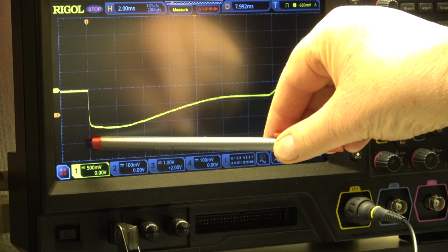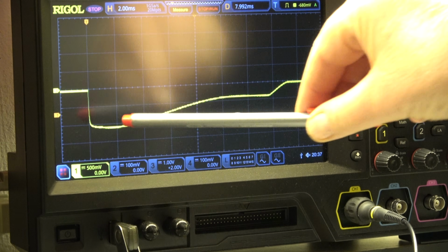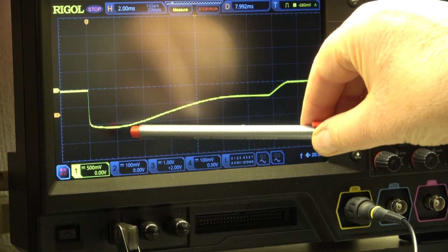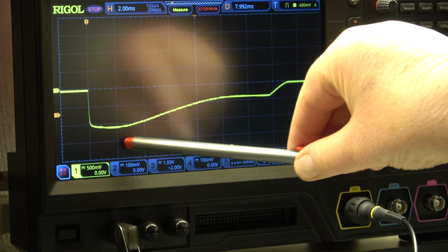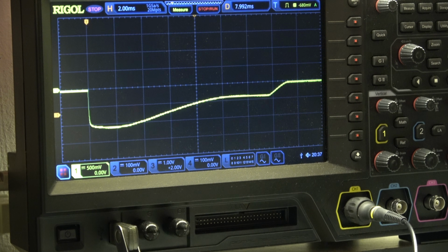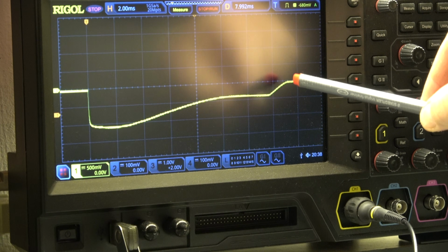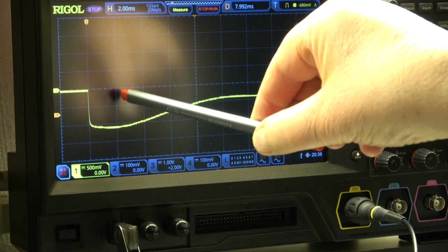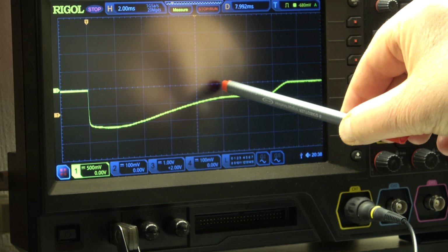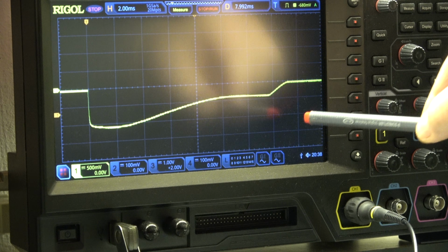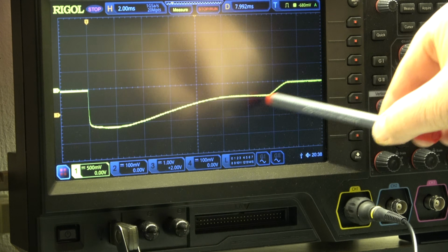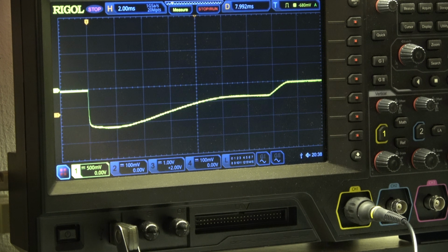We have here 500 millivolt times 10, 5 volt per division, so we have 10 volt. Shunt is 1 ohm, so we have a peak current of 10 amps for a certain time, and this is now the discharge curve of the filter capacitors in the power supply on the rectifier side. And here after we have 2 milliseconds per division, 2, 4, 6, 8, 10, 12, 14, 15. After 15 milliseconds, the current is switched off internally by the automatic overcurrent protection.